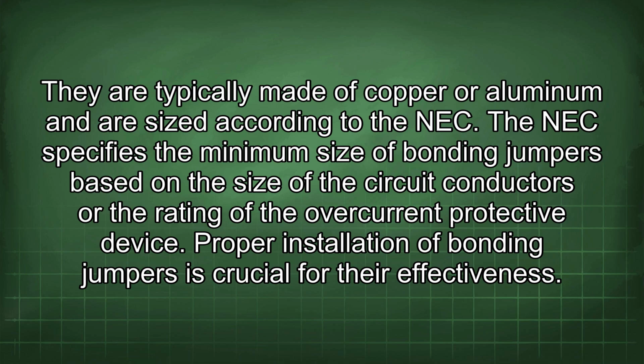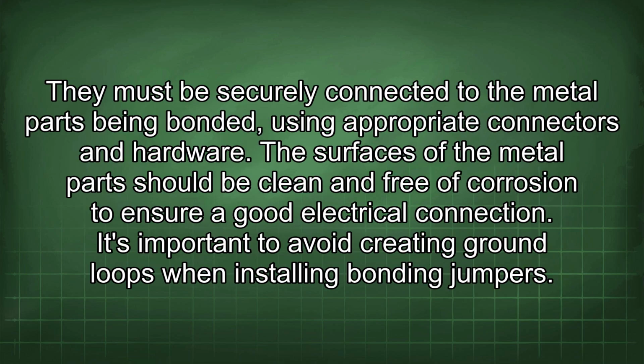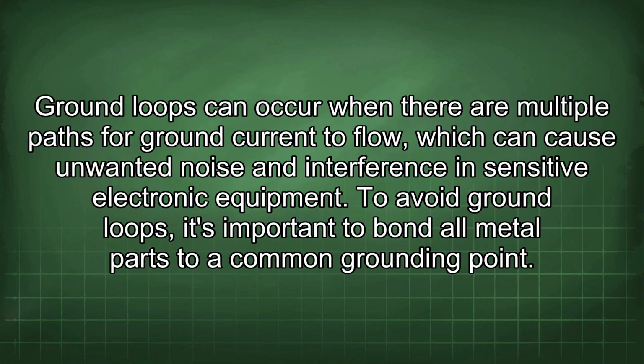Proper installation of bonding jumpers is crucial for their effectiveness. They must be securely connected to the metal parts being bonded using appropriate connectors and hardware. The surfaces of the metal parts should be clean and free of corrosion to ensure a good electrical connection. It's important to avoid creating ground loops when installing bonding jumpers. Ground loops can occur when there are multiple paths for ground current to flow, which can cause unwanted noise and interference in sensitive electronic equipment.